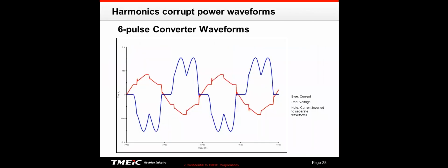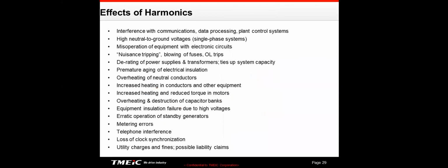Now, this is a standard 6-pulse converter. We could think of this more as a low voltage drive, although some medium voltage drives can look like this as well, but not too many of the quality ones. And you can see that current is anything but a sine wave. And so because the current is distorted like that, it's going to generate high frequency noise. And when you think of harmonics or bad power, generally we're talking about high frequency noise that is being created by the drive and being put back on the power distribution system.